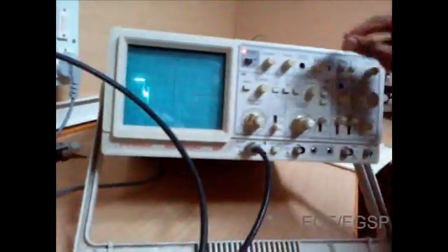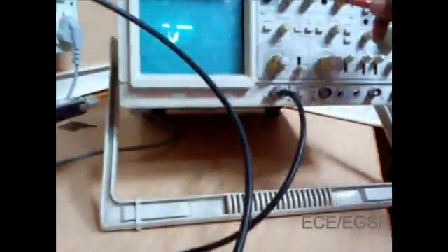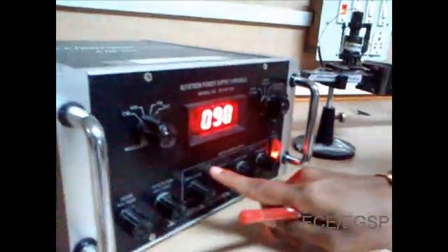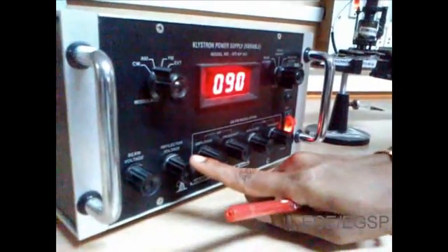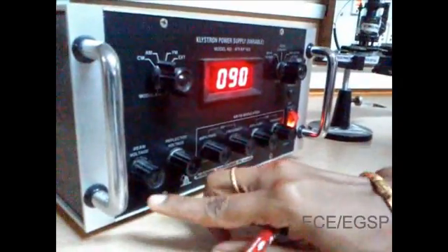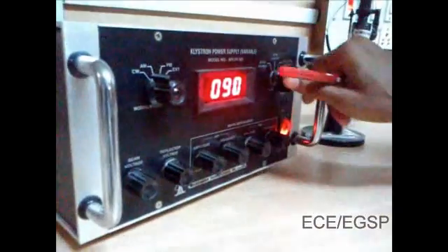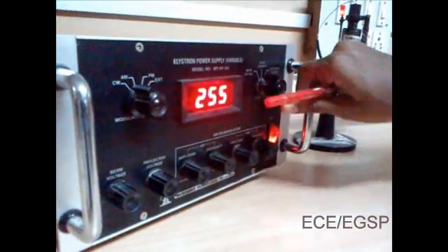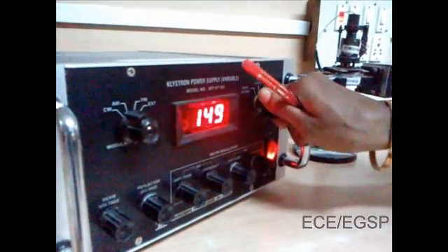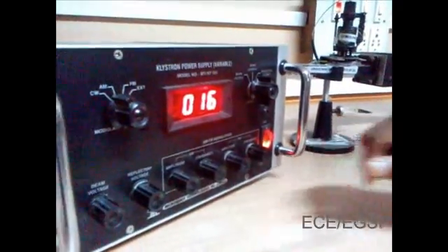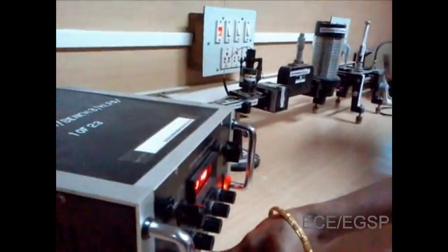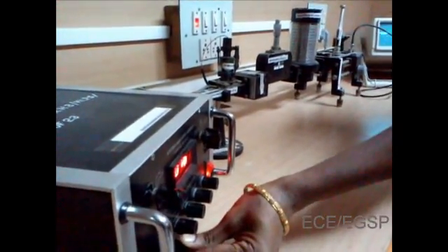The detector mount is attached to a CRO. To get a square wave in the CRO, you have to set some ranges in beam voltage level and reflector voltage level. For that, beam voltage should be 250. Beam current should not exceed 30 milliamps. By adjusting reflector voltage, you have to get a square wave in the CRO.